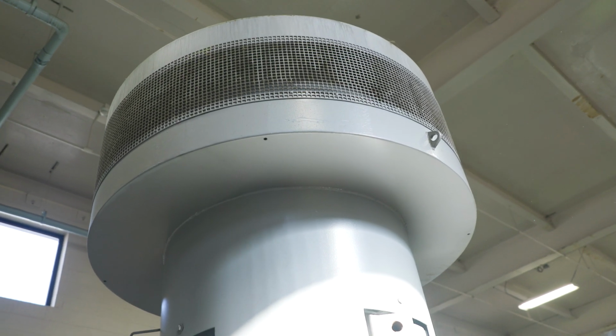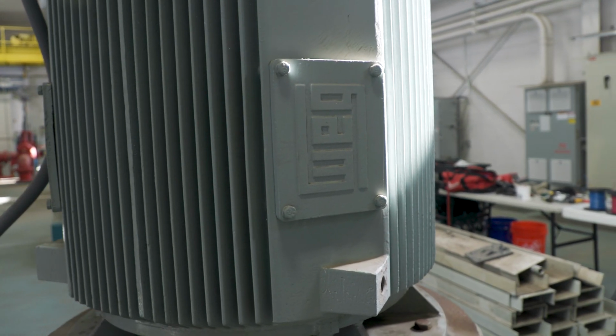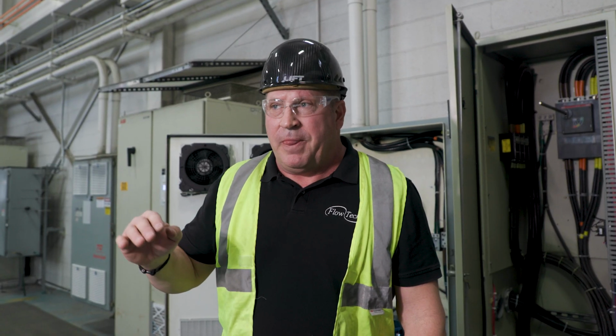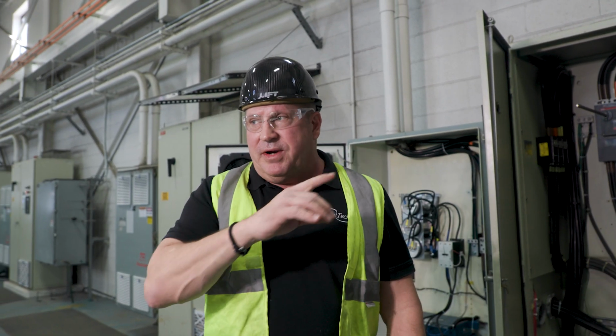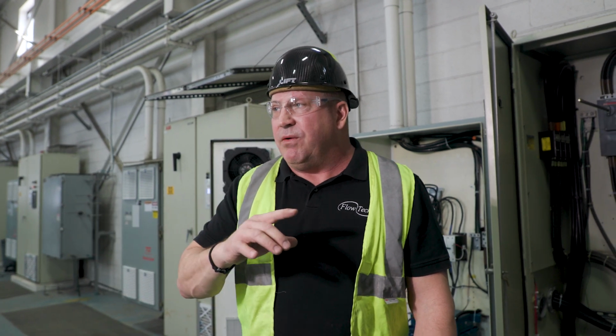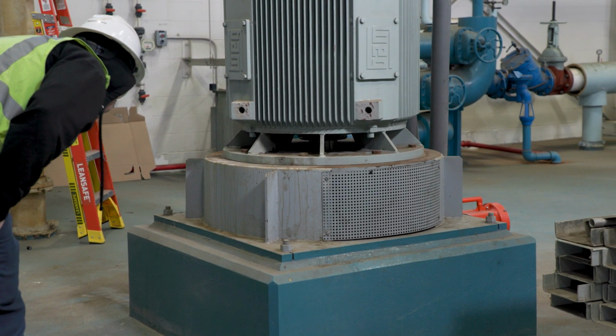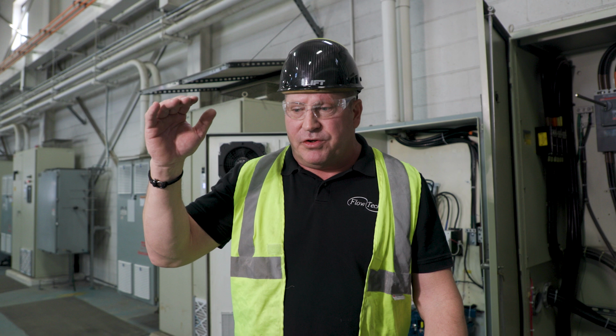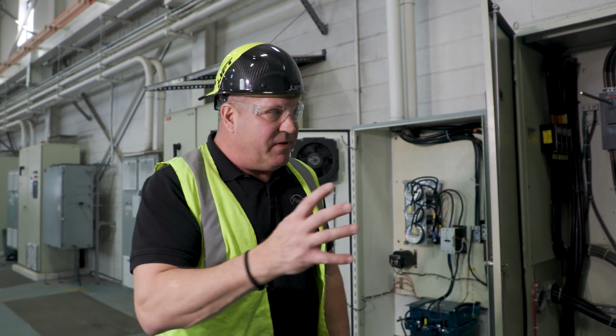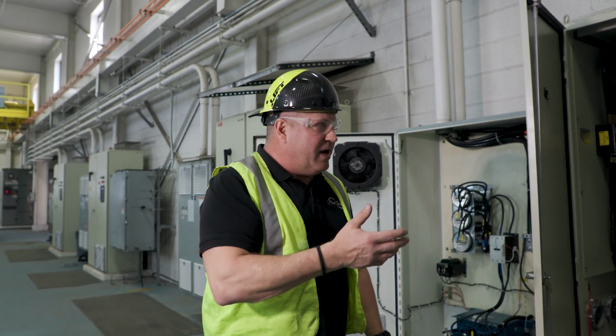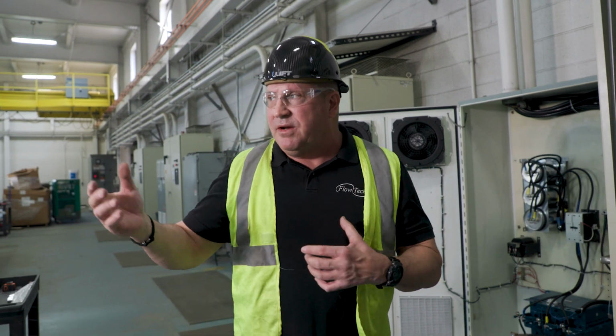It goes through a process and then gets gravity fed over to here. It's running off tank level. And then it goes out to the primary tanks as it pumps it out. So tank level is important. You can't just run these motors full out or you'll drain the tank. So that's why we have a VFD involved, which controls the speed of the motor.